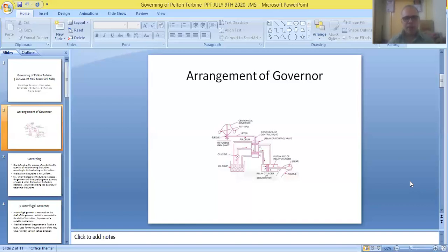And finally, when the piston of the servomotor is moving in forward direction, the oil that is present on the right hand side of the piston will be leaving the servomotor, and it will be entering from the top of the first cylinder, and through the top pipeline, this quantity of oil which is entering the first cylinder will be going back into the oil reservoir.